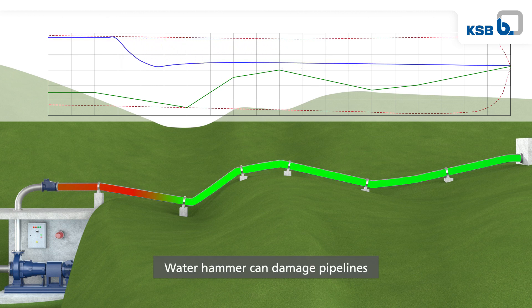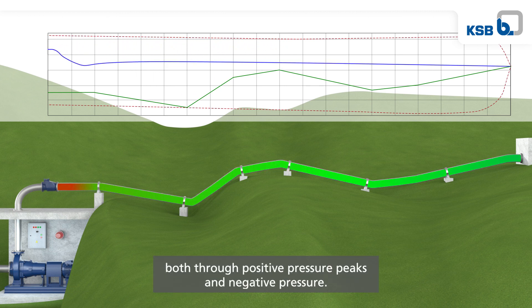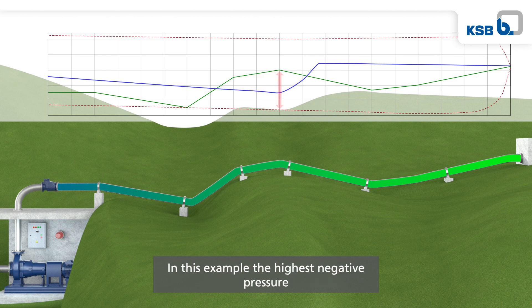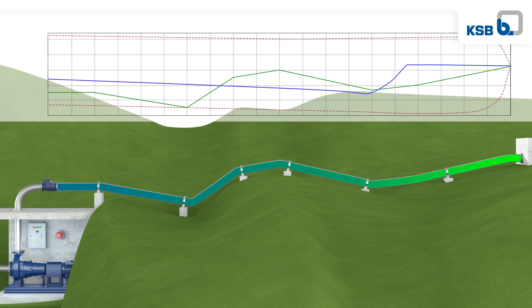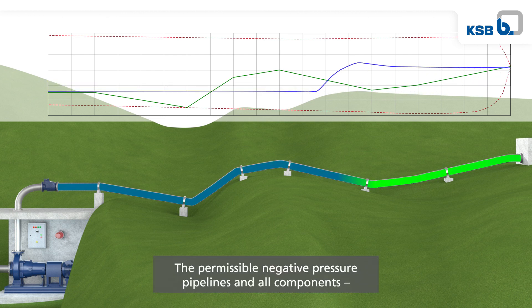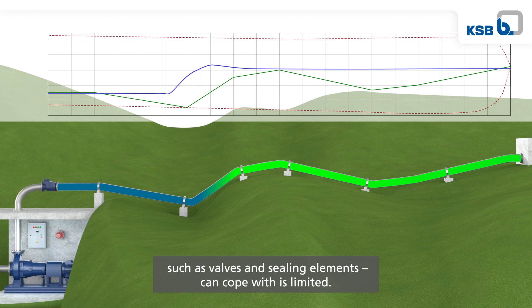Water hammer can damage pipelines both through positive pressure peaks and negative pressure. Whenever the pressure head curve is below the geodetic head of the pipeline, negative pressure is present. In this example, the highest negative pressure occurs at the high point in the middle of the pipeline section. The permissible negative pressure that pipelines and all components such as valves and sealing elements can cope with is limited.